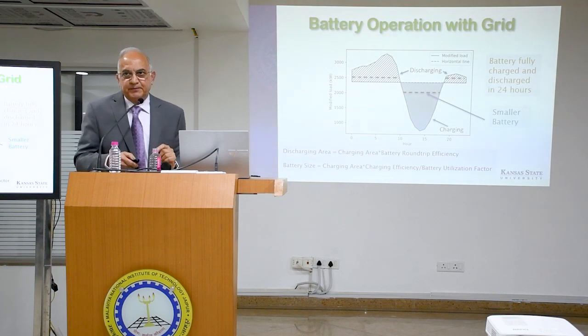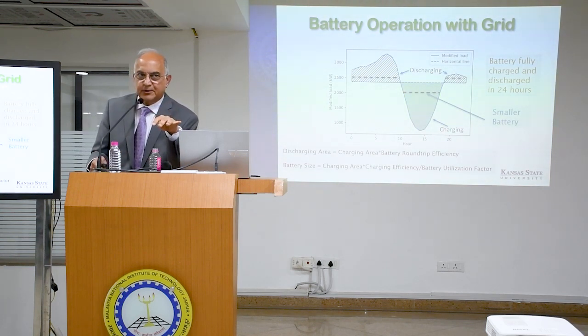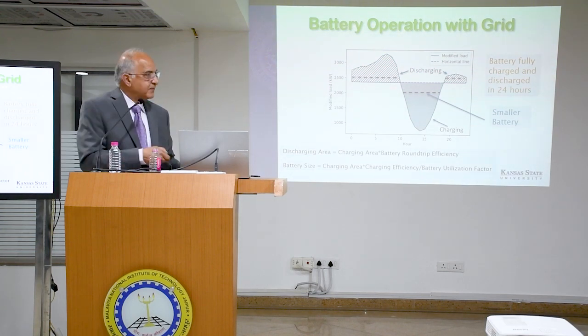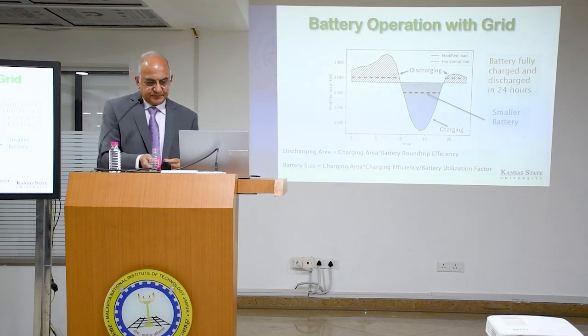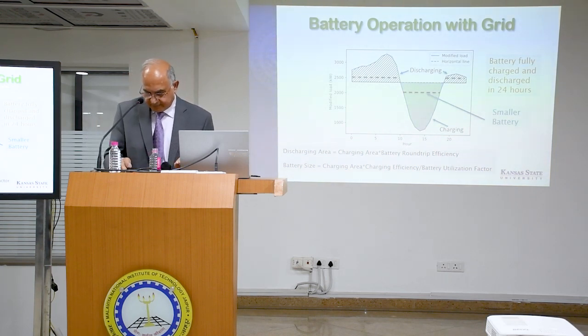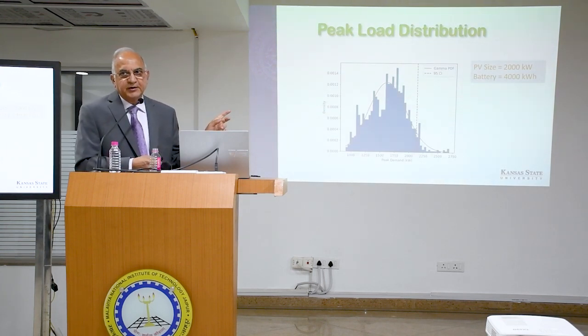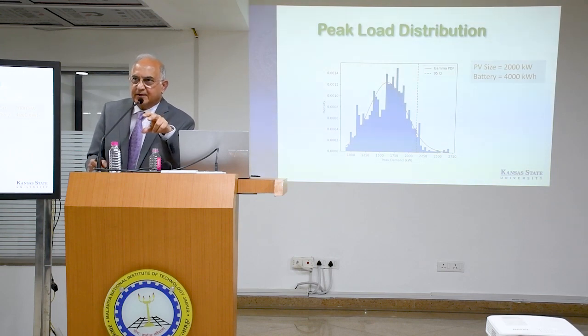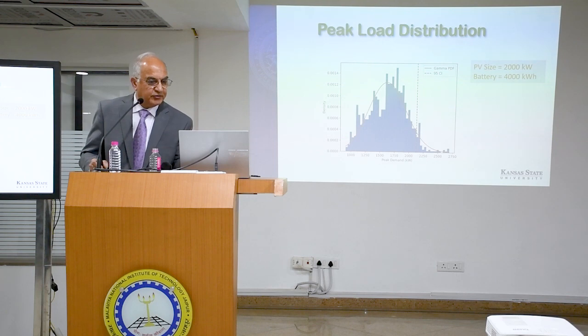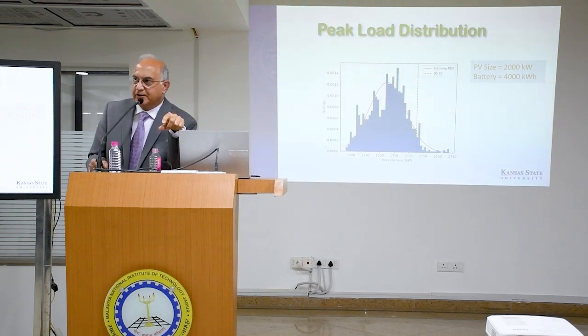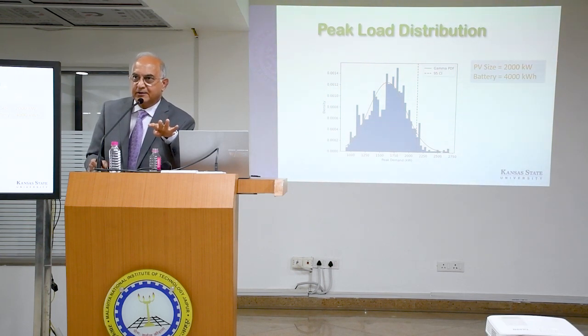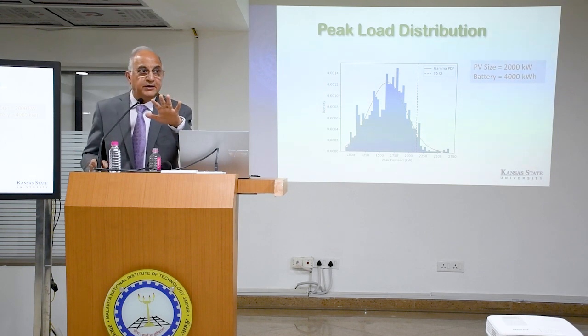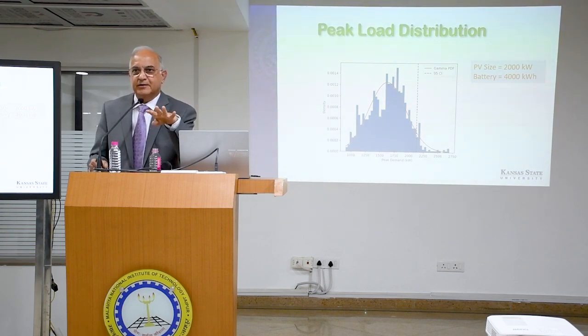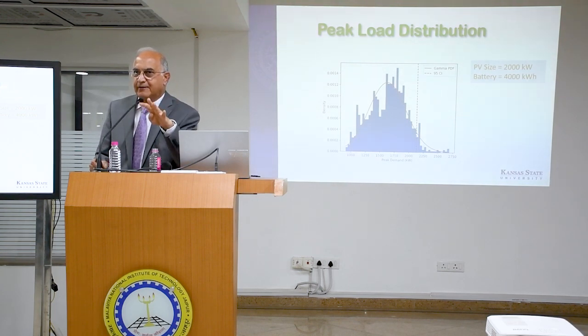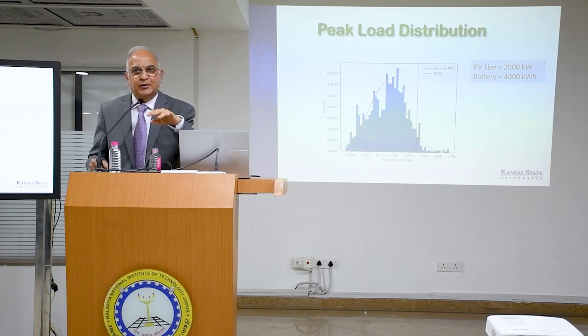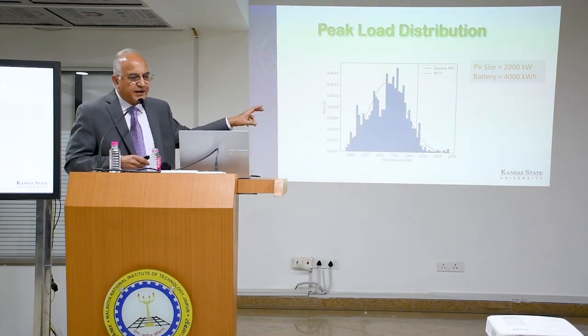So what we did is we picked different battery sizes and different solar PV sizes, and I'm going to show you an example. This is the graph that shows implementing solar PV and battery of this size - an example where we chose PV of 2000 kilowatts and a battery of 4000 kilowatt hours. Then we looked at actual data of 3 years, implemented for every day of the year the battery, and calculated the new peak load, and this is the graph you get.